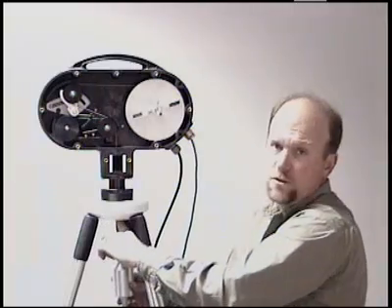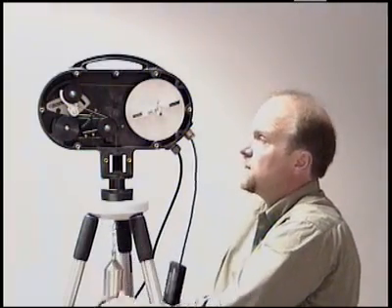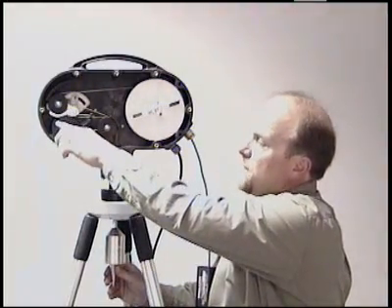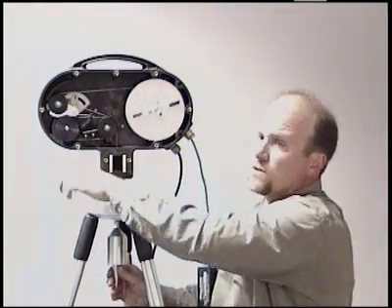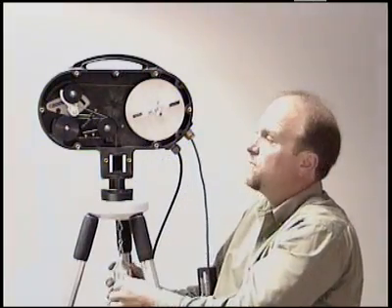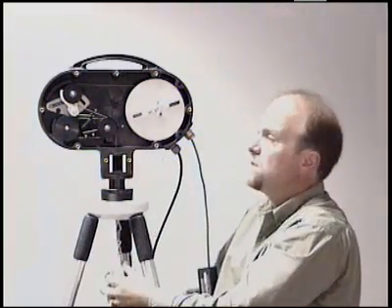and pulls the sensor probe back up to the neutral position at the top of the vessel. So it basically goes down, the idler arm comes all the way back, brakes the timing pulley, stops the pulses and pulls the sensor probe back to the neutral position at the top of the vessel. And this is all done instantaneously.